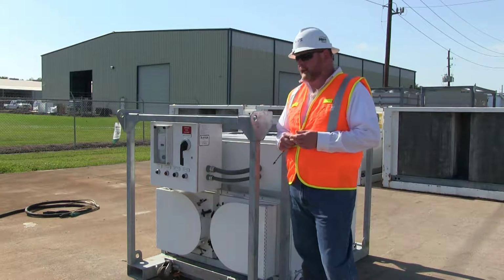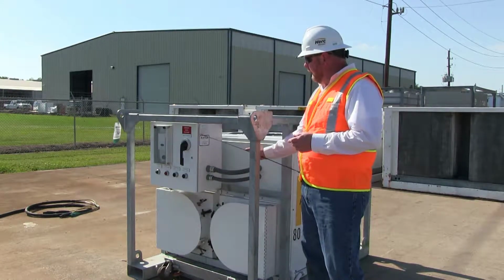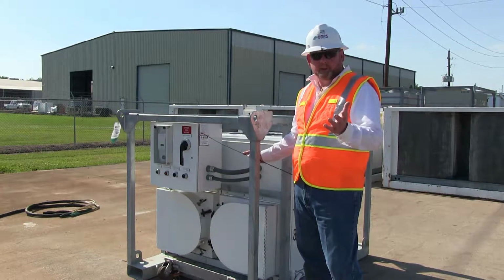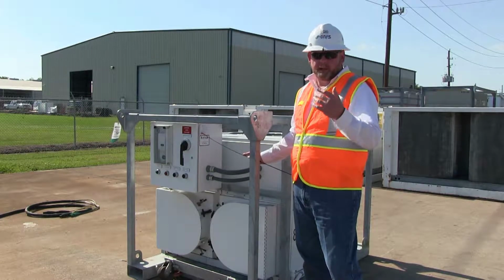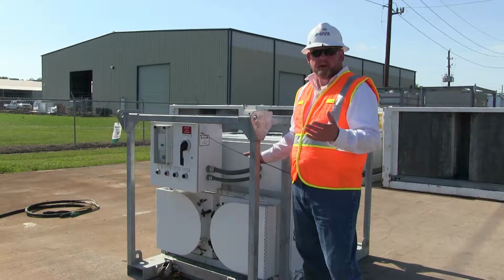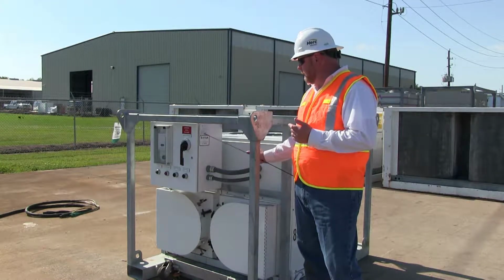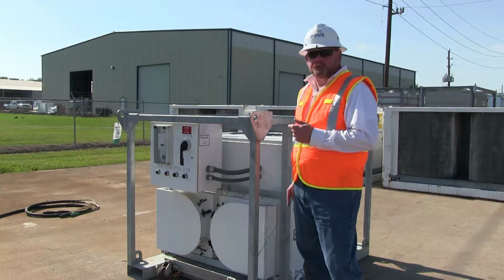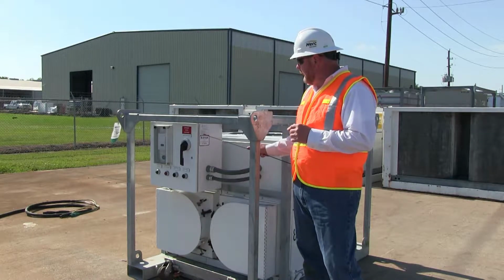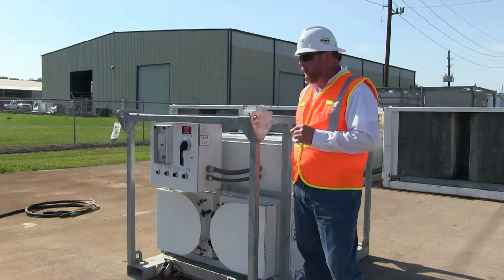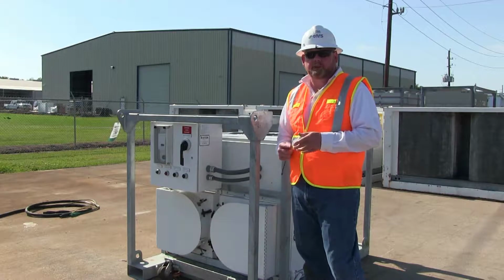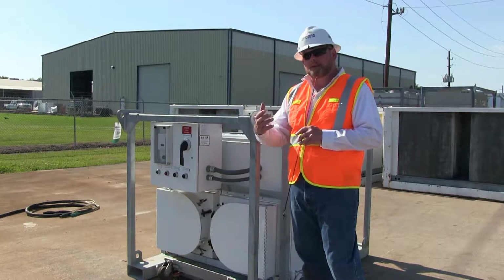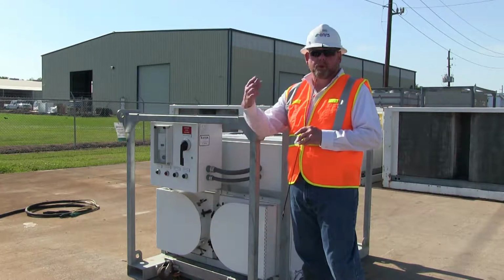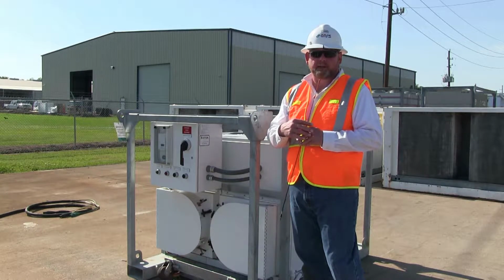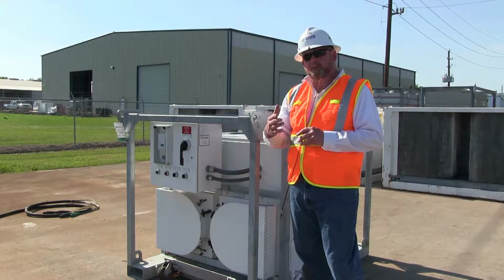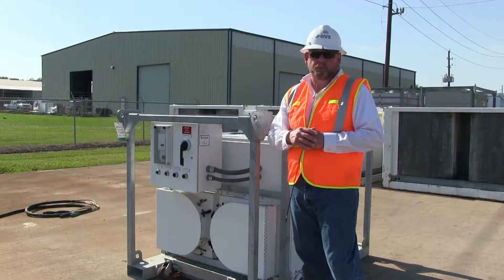That's all clearly identified on the data tag here under the MCA, which is minimum circuit ampacity, and MOCP, maximum overcurrent protection. For instance, the cooling for this machine requires 14 amps, the heating is 31 amps, but in dehumidification mode it takes 41 amps to run the machine. So when you're loading it in, you want to make sure that you have adequate power for the mode that's being required for the project. You always want to size your power supply for whatever the job calls for.